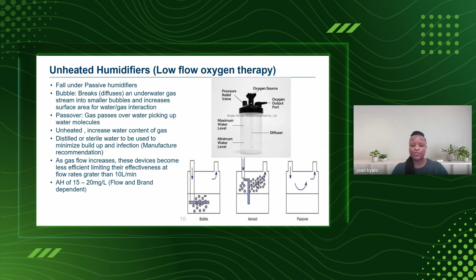And then this is obviously unheated, and it is important to use distilled water, because a lot of this is going to end up as aerosols into the patient's upper respiratory system. So it's really important. And also a lot of these bubblers will come with a manual. It's important to read it and refer to it. And then another thing is that we have the passovers, and also the active humidifier that we'll talk about later has a similar sort of passover mechanism, but in this one, some have a membrane, referred to as the wick, and then we also have a semi-permeable membrane where the gas interacts with a membrane that holds water content and picks up some, and leaves to go as an output.